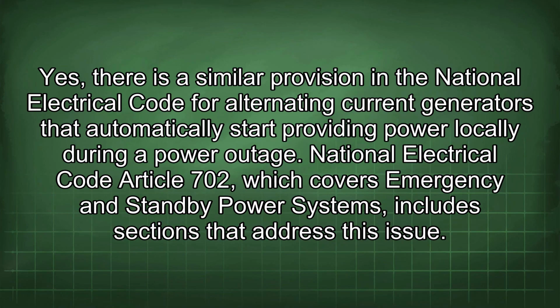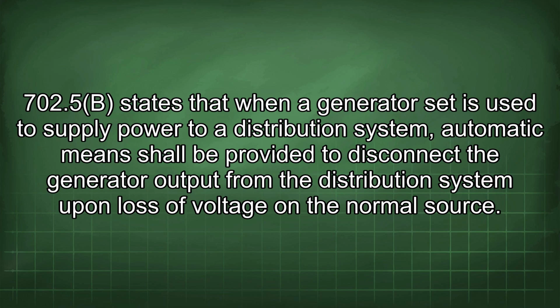Yes, there is a similar provision in the National Electrical Code for alternating current generators that automatically start providing power locally during a power outage. National Electrical Code Article 702, which covers emergency and standby power systems, includes sections that address this issue. 702.5b states that when a generator set is used to supply power to a distribution system, automatic means shall be provided to disconnect the generator output from the distribution system upon loss of voltage on the normal source.